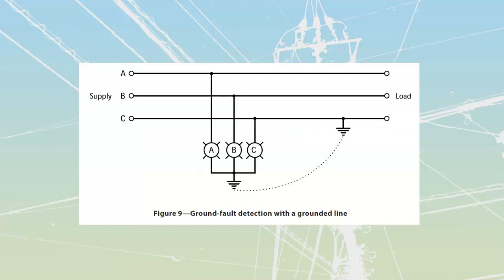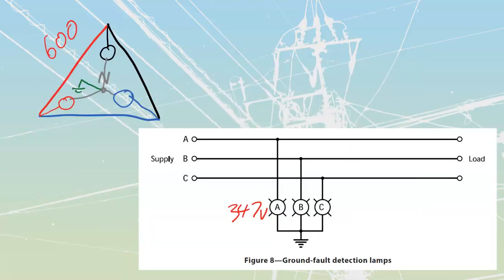As soon as there's a fault on the system, one of these lines on the actual delta system gets brought to the same potential as ground. Remember, everything is floating around that ground.